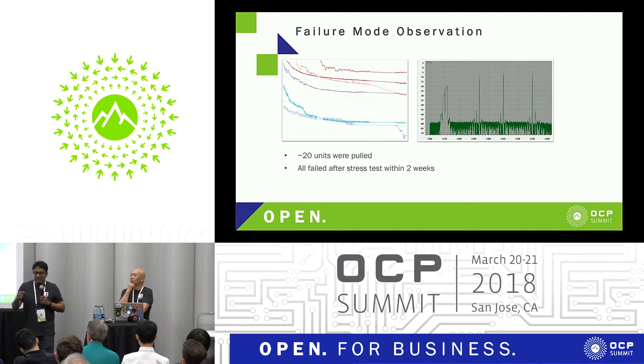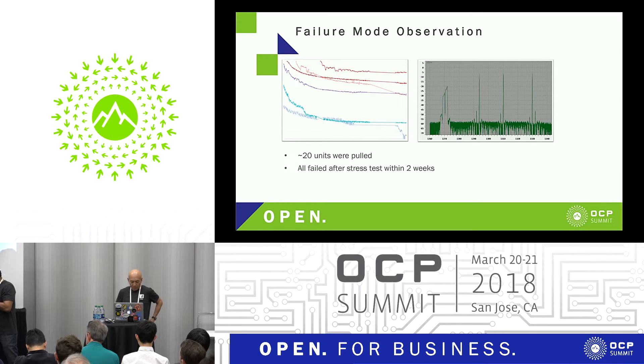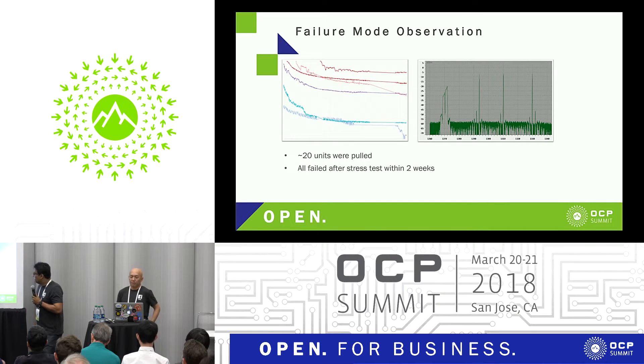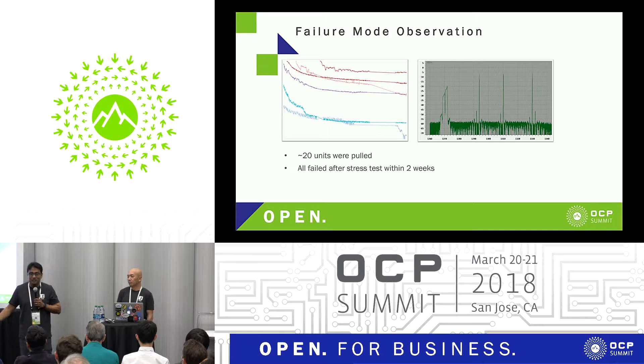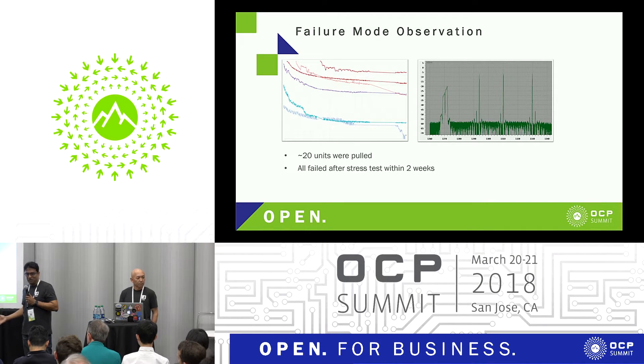That module is going to fail in the next two weeks, three weeks, or a month. We collected several samples based on this graph and did some aggressive testing at our facility, and found that most parts failed in two weeks. This is an indicator — not the ultimate solution — but a way we can predict and at least save some failures at our data center.